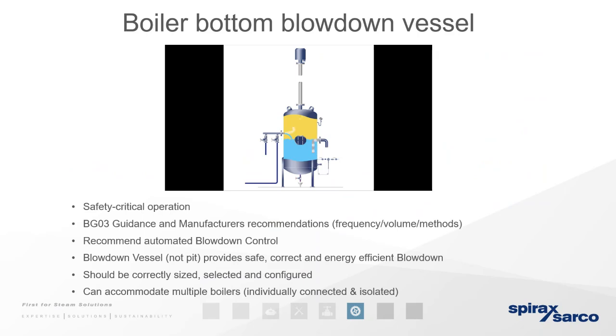So bottom boiler blowdown needs to be collected somewhere. In Europe, I think the legislation is similar in parts of Africa, but we can't blow down water to drain any higher than 43 degrees. So we need to put that somewhere to be able to cool down before we release it to drain. So that's where our bottom blowdown vessel comes in.